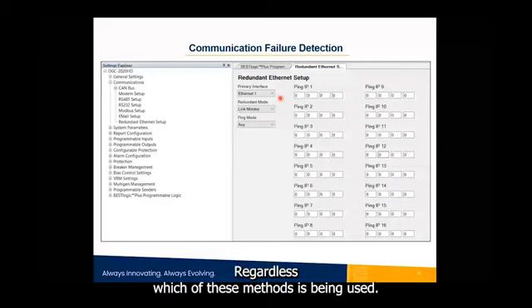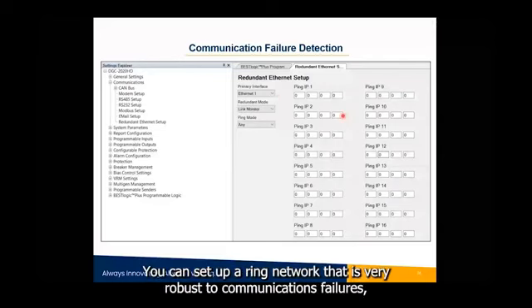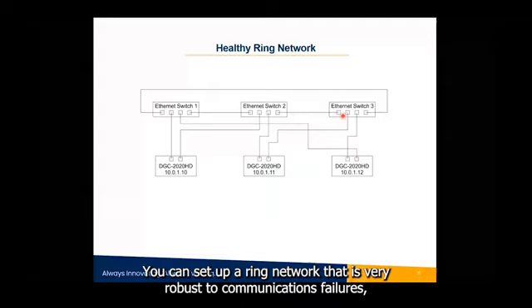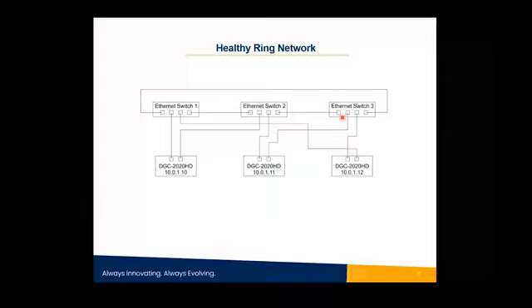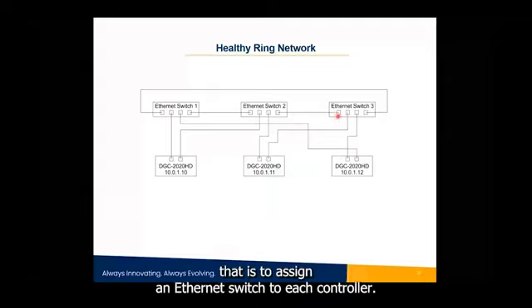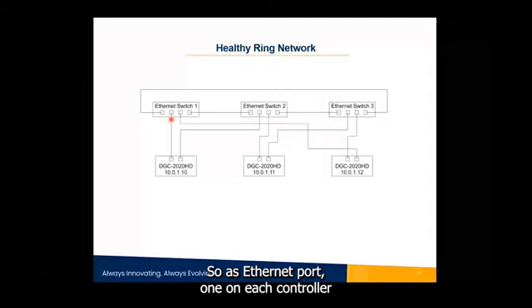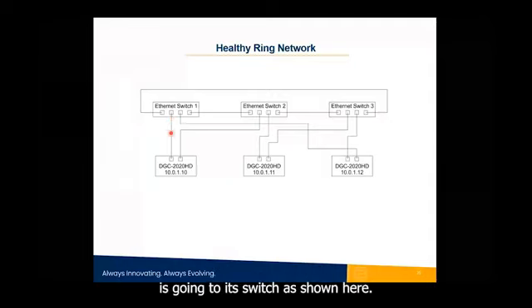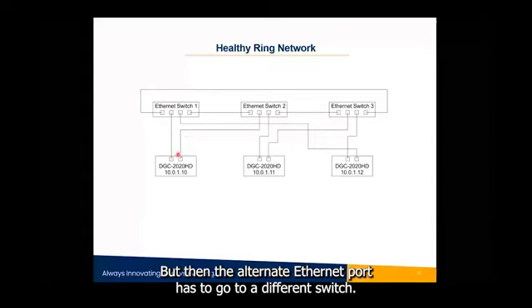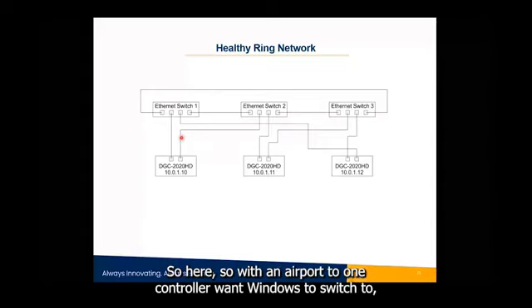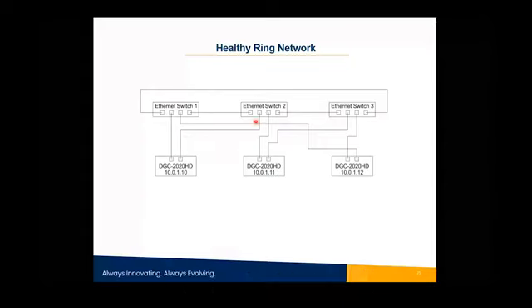Regardless of which of these methods is being used, you can set up a ring network that is very robust to communications failures. And the way you would do that is to assign an Ethernet switch to each controller, but you use both Ethernet ports. So if Ethernet port 1 on each controller is going to its switch, as shown here, but then the alternate Ethernet port has to go to a different switch, as shown here. So Ethernet port 2 on controller 1 goes to switch 2.